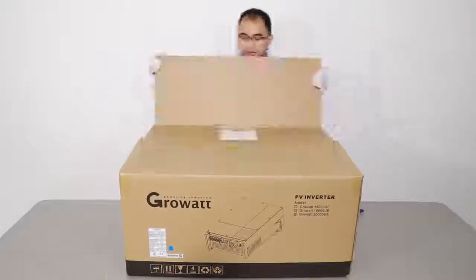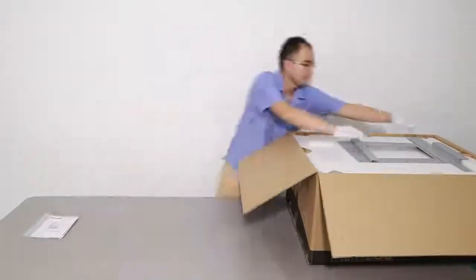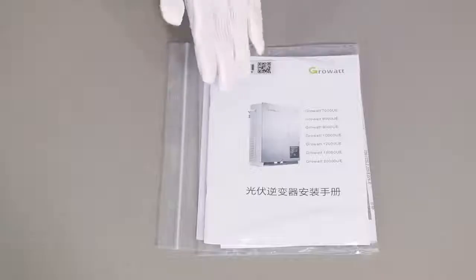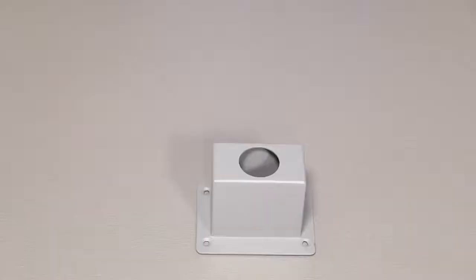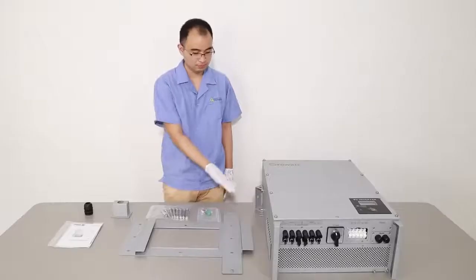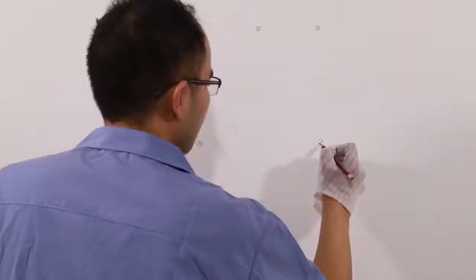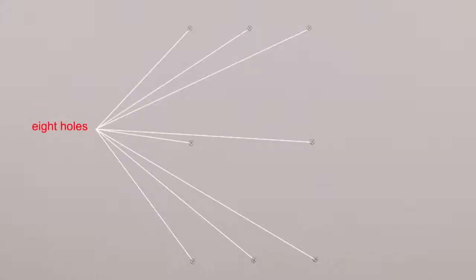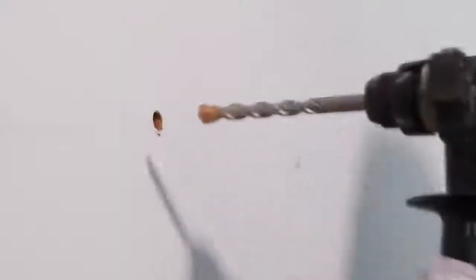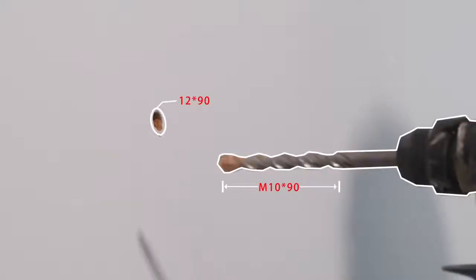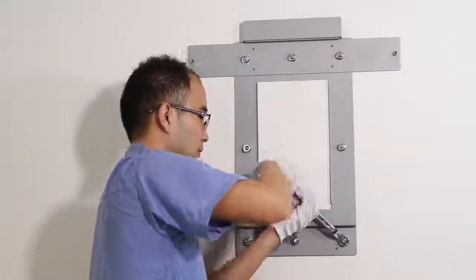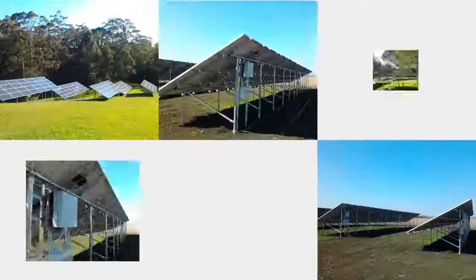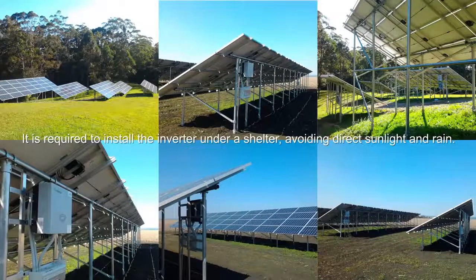Unpacking and checking. Unpack the packing. Take out the accessories and the inverter. According to the accessories listed on the manual, check whether there is any missing. Follow the installation manual to drill holes. And hang inverter to the wall. Do not forget to screw the safety screws firmly. It is required to install the inverter under a shelter, avoiding direct sunlight and rain.